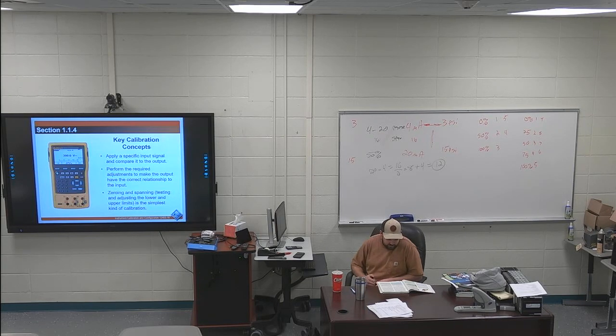When you zero the instrument, you set its output value to its minimum range limit, which represents a zero input from the process. For example, consider a pneumatic transmitter used with a process whose range is 20 to 150 inches of water. The zero value is 20 inches of water. If the transmitter's output range is 3 to 15 psi, its zero value is 3 psi. At 20 inches of water, input to the transmitter should produce an output of 3 psi. If it doesn't, you must adjust the output until it does. You will do this on the lab that's right there.